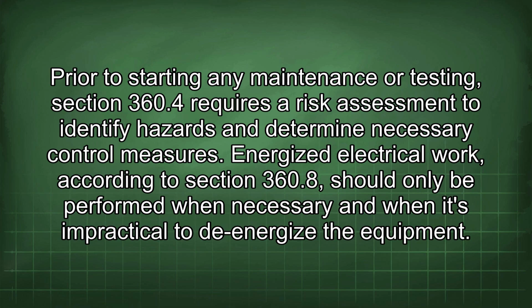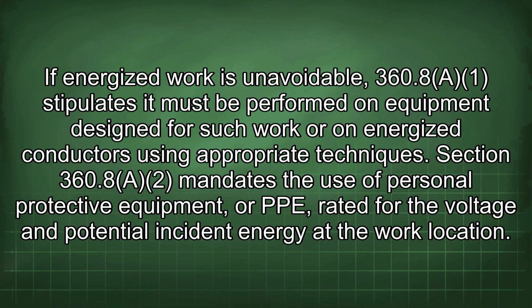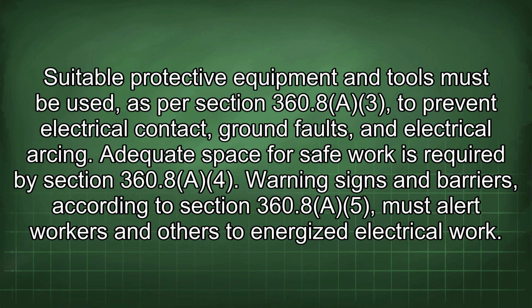Energized electrical work, according to Section 360.8, should only be performed when necessary and when it's impractical to de-energize the equipment. If energized work is unavoidable, 360.8A1 stipulates it must be performed on equipment designed for such work or on energized conductors using appropriate techniques. Section 360.8A2 mandates the use of personal protective equipment, or PPE, rated for the voltage and potential incident energy at the work location. Suitable protective equipment and tools must be used as per Section 360.8A3 to prevent electrical contact, ground faults, and electrical arcing.